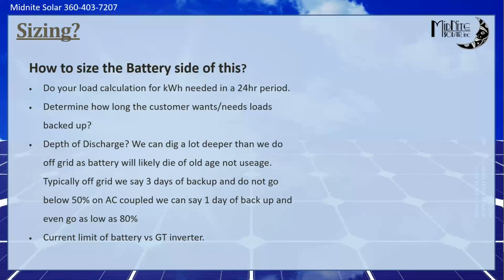You can dig deeper, of course, into a lithium. There are tons and tons of charts. We have published documentation, I believe, on our PowerFlow that will tell you the difference between draining it to, say, 25% state of charge regularly or 50% state of charge, like 75%. There is a difference in cycle life, but you have to calculate, is that difference better to oversize the battery and dig shallower, or is the cost of the additional battery outweighed by digging deeper into that battery? So you have to balance that out based on cycle life.